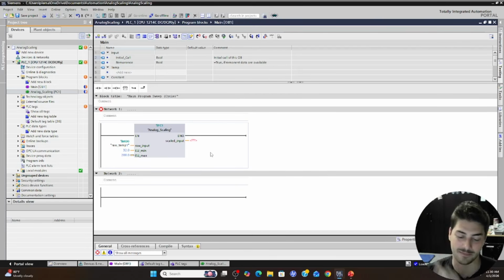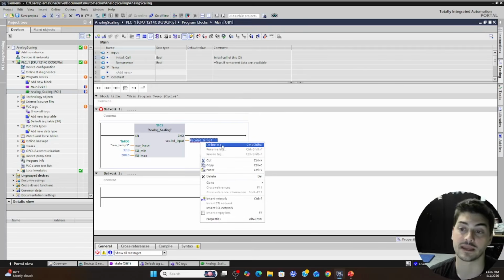This should be from the manual of the device that you hooked up. So depending on the specs of your temperature sensor, your flow meter, it'll tell you min span and max span for 4 and 20 milliamps. So I am obviously picking values for the demonstration, but these are things that should be coming from a manual.